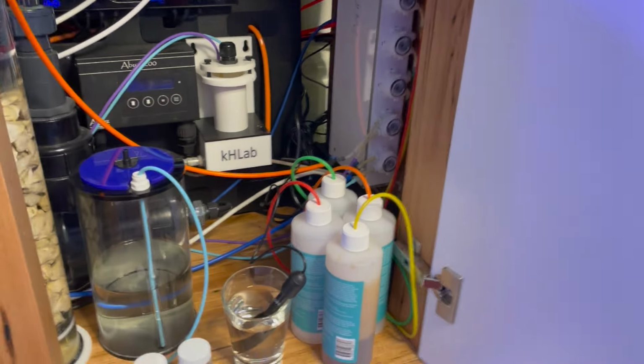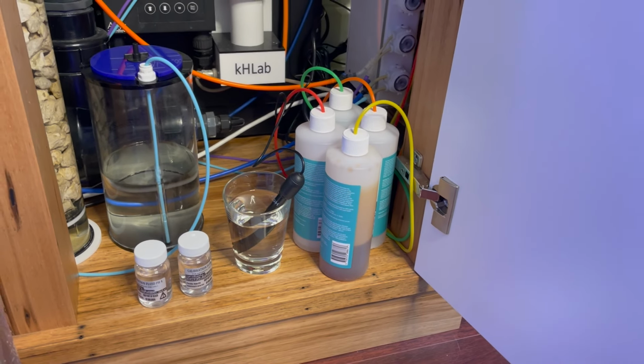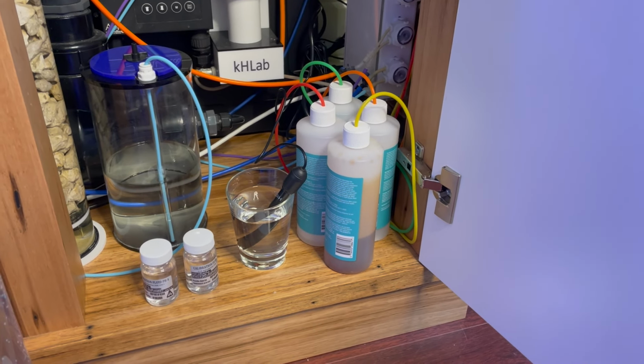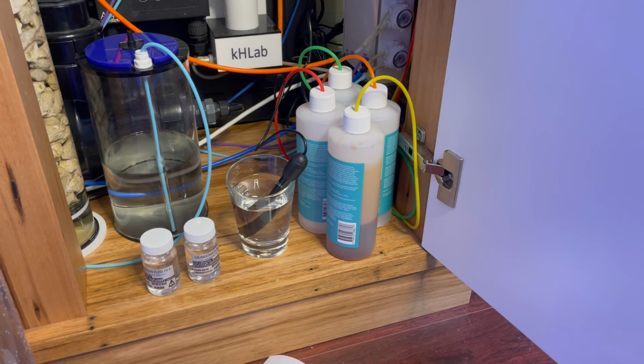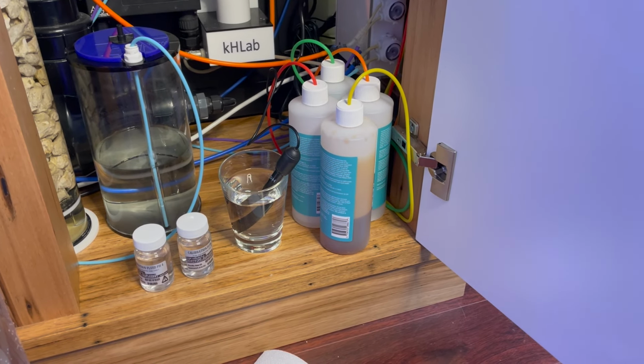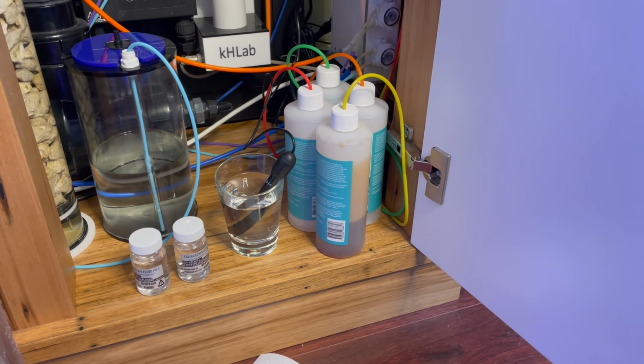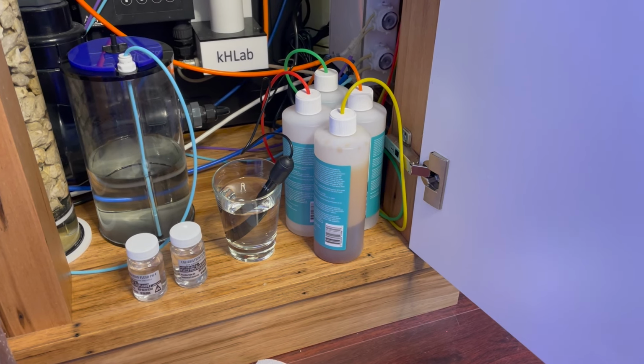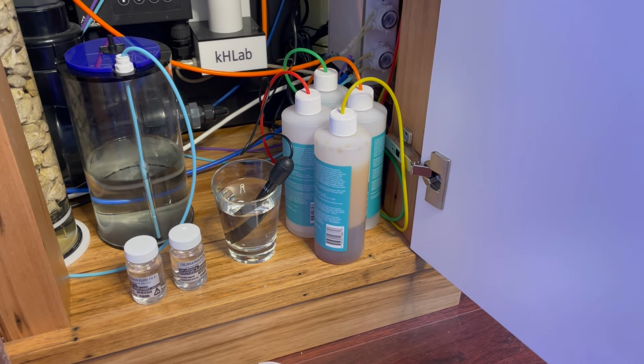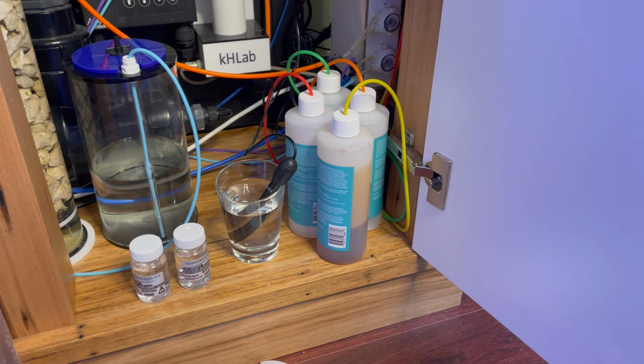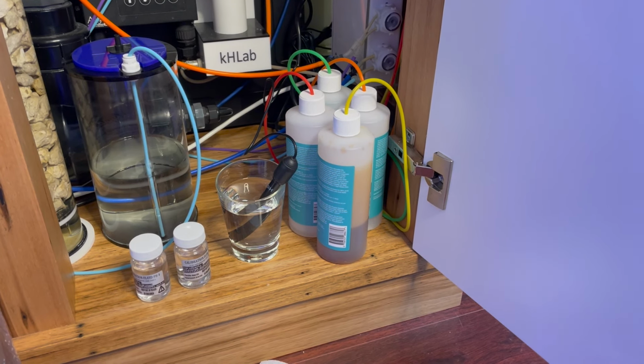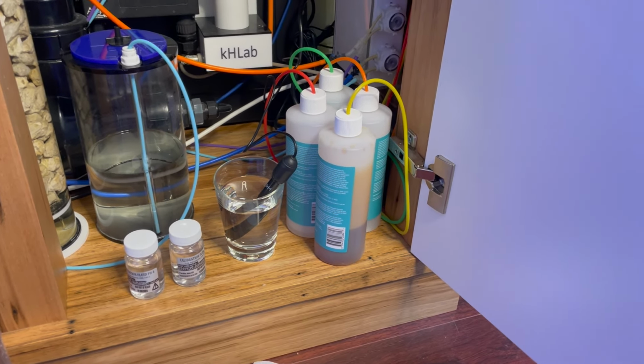Now, one thing to note, if you are adding a pH probe or only replacing one of the pH probes, you do need to recalibrate both of them because the calibration will swing dependent on whether there is 1 or 2 probes plugged into the unit. So they both need to be calibrated at the same time. All right, let's get started.